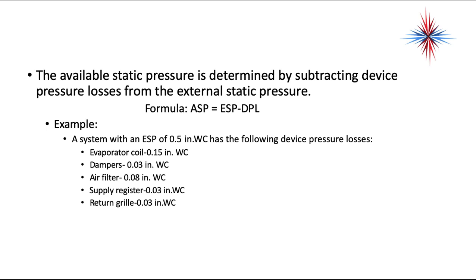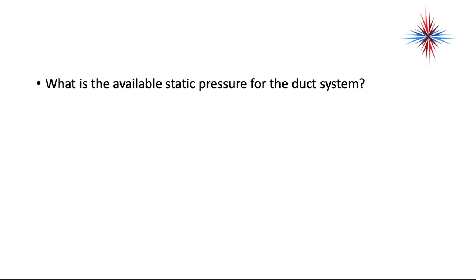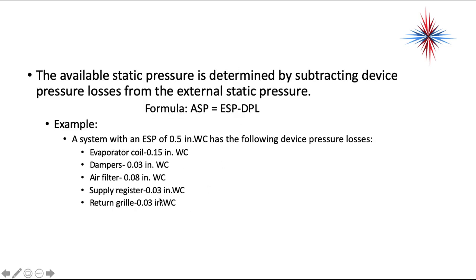The available static pressure is determined by subtracting the device pressure losses from the external static pressure. For example, with an external static pressure of 0.50 inches water column and device losses of: evaporator coil 0.15, dampers 0.03, air filter 0.08, supply register 0.03, and return grill 0.03 — totaling 0.32 — the available static pressure is 0.18 inches water column. The ductwork on the return and supply must be designed within that 0.18 inches water column.